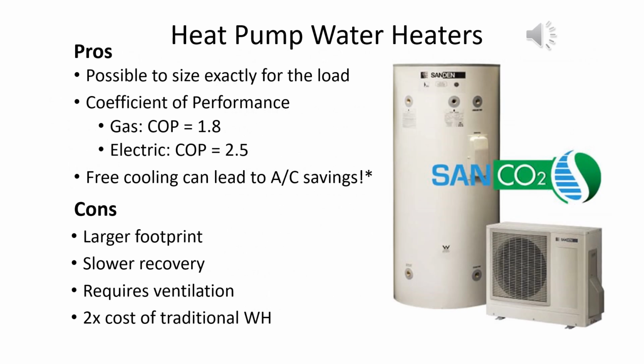If California continues to decarbonize, heat pump water heaters are likely to become the most common type of water heater in commercial food service facilities. Heat pump water heaters boast a coefficient of performance as opposed to a thermal efficiency. They siphon energy from the air and their surroundings to heat water. An electric heat pump water heater with a COP of 2.5 would produce 2.5 kilowatt hours of useful water heating for every kilowatt hour consumed at the wall. This would provide very large energy savings over conventional gas water heaters and could, in some cases, be enough to offset the higher fuel cost.